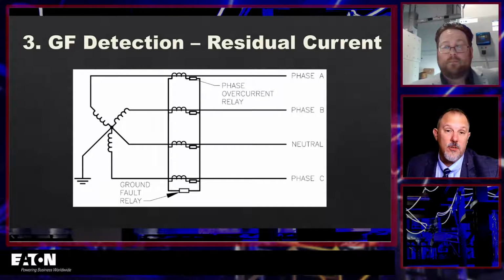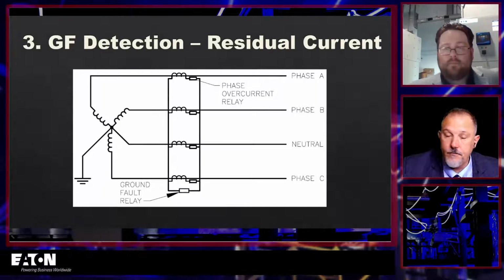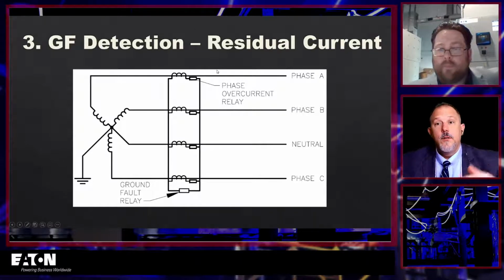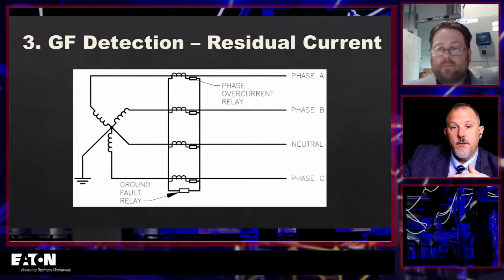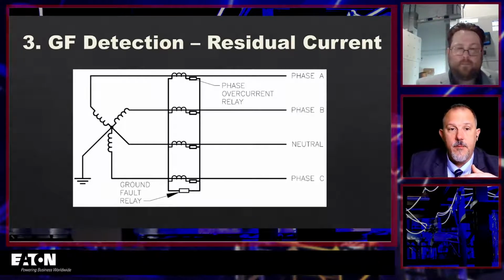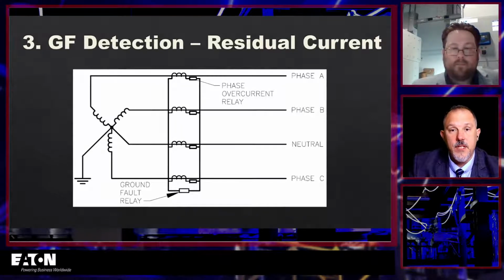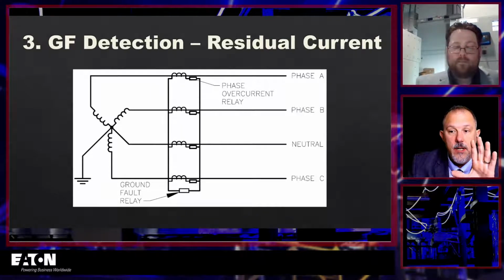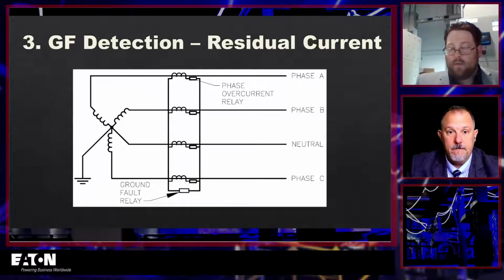Sometimes it depends on what you're doing and what you're changing out. So residual versus zero sequence versus monitoring that return, all three of those are different methods to achieve the same goal, and they would all be tested differently.